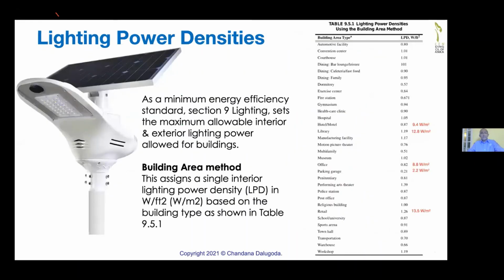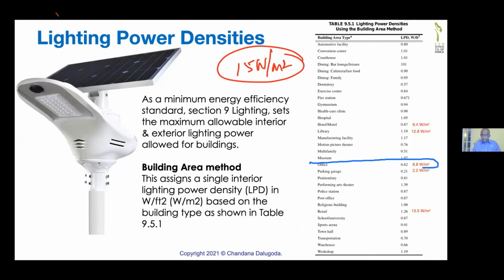Not even that. Lighting power densities. Now usually a non-certified building has a lighting power density of 15 watts per square meter. Normally we take this for our cooling load calculations. But you can see now the ASHRAE target, let's see, office, 8.8 watts per square meter. How do we do that? You'll have to find light fixtures with lower power.